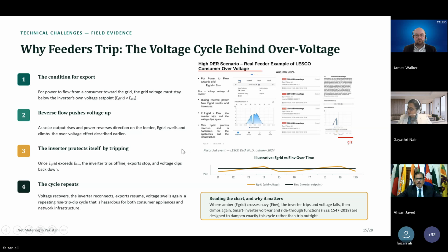Unfortunately, the inverters that were there in 2015 were not designed to cater for this behavior. But after 2018, IEEE 1547 was revised, and the inverter standards were updated to cater for this effect: to reduce their power on their own, to ride through that fault level or voltage, and to maintain this distance between the E grid and the E inverter. But the issue here is that, unfortunately, in Pakistan the capacity building of the local installers is not up to that level.